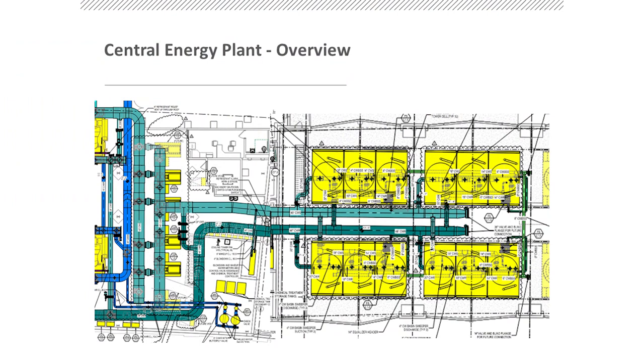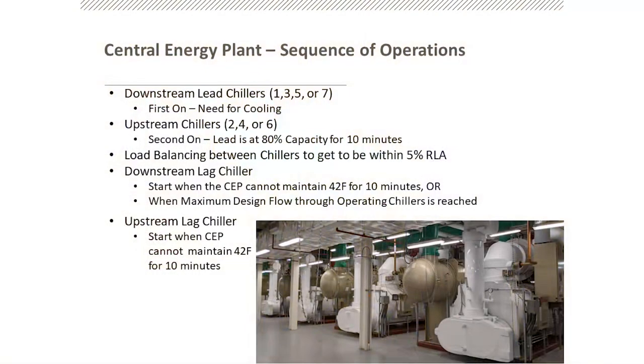And then it serves 3 different loops leaving the plant. And those loops, as you can see, the pipe size is there. So in essence, this plant is N+1 redundancy, built in for a little bit of resiliency. And I'm going to show you the next picture, which essentially is the cooling tower lineup and everything else, just so you know that I wasn't lying about the equipment that's in this plant. But pretty impressive. But when you talk about a chiller plant, you really want to talk about how does a chiller plant actually work? What was the intended operation for these machines, right?